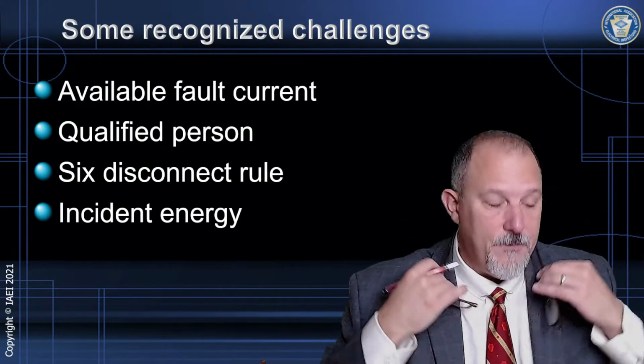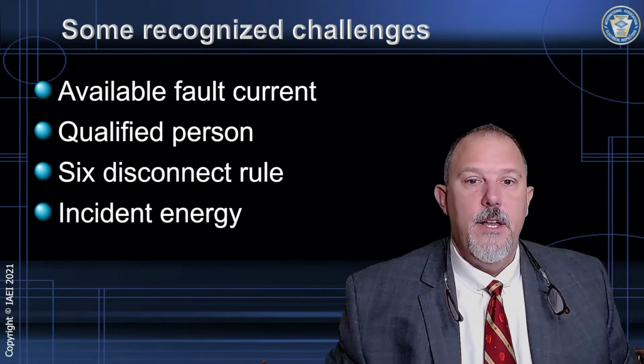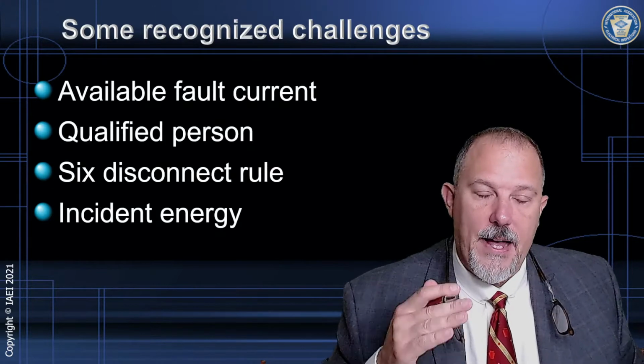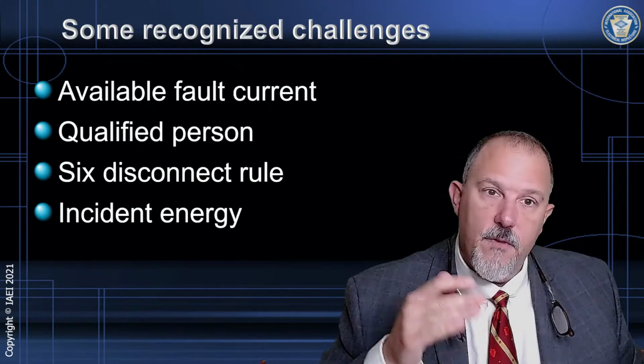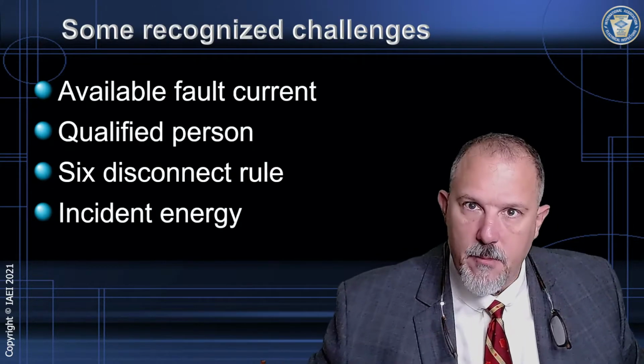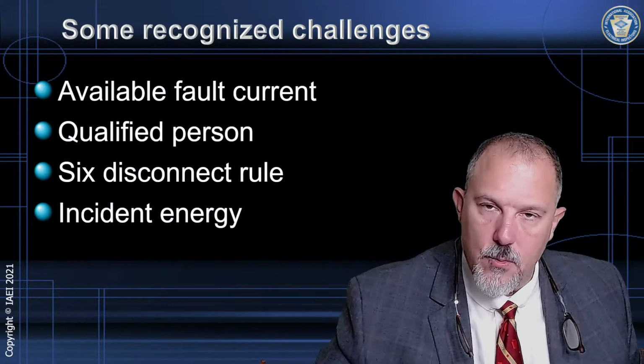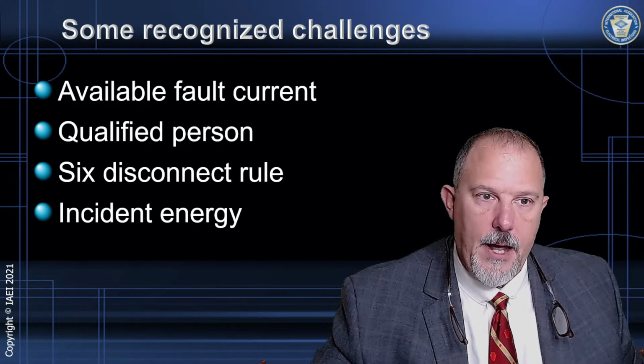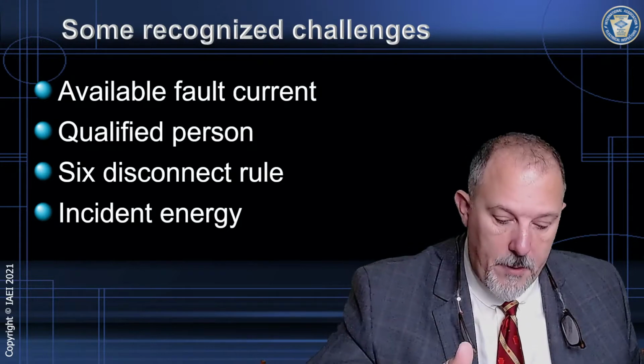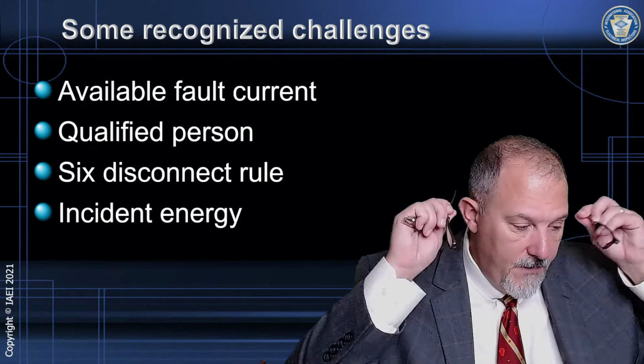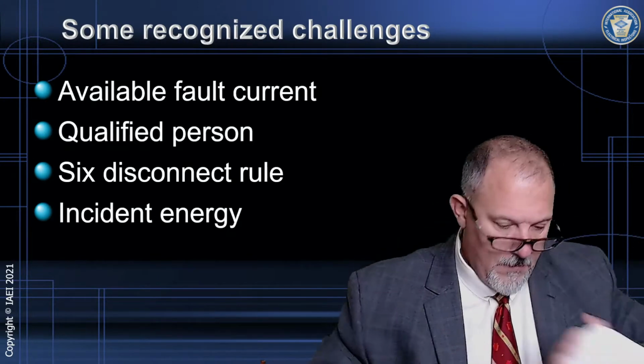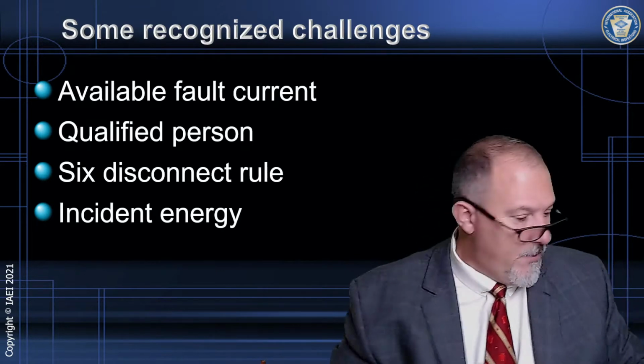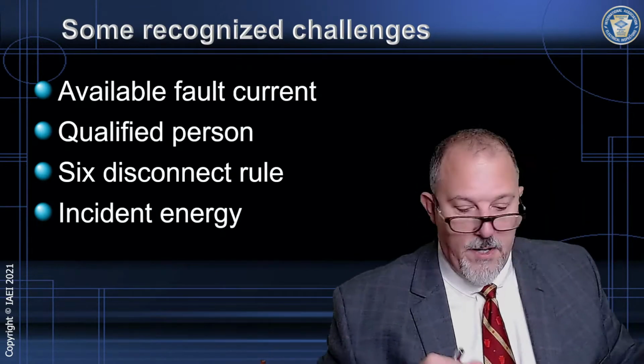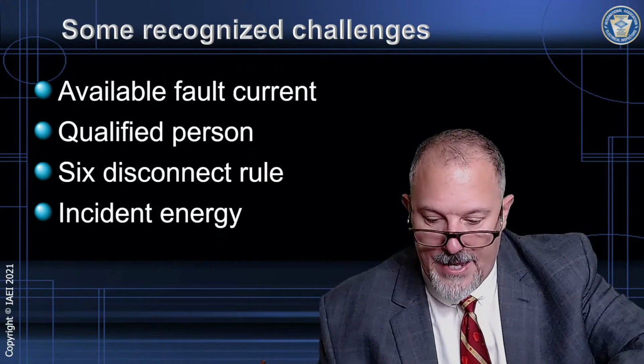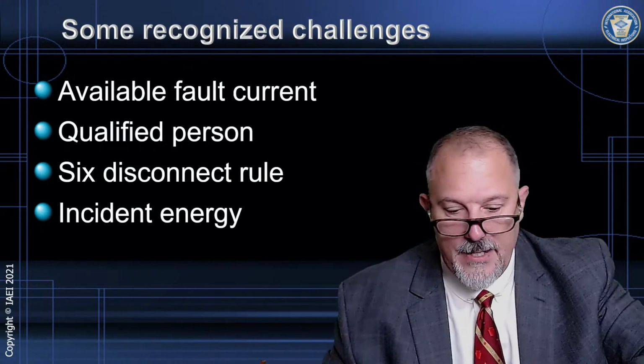And why is that? Because they realized that, look, the available fault current, it's not the maximum available fault current, it's an actual available fault current. And then who is going to be putting these labels on? If I look at, see, that's the 17. I'm going to grab the 2020 version just to see where we're at today, 110.16.